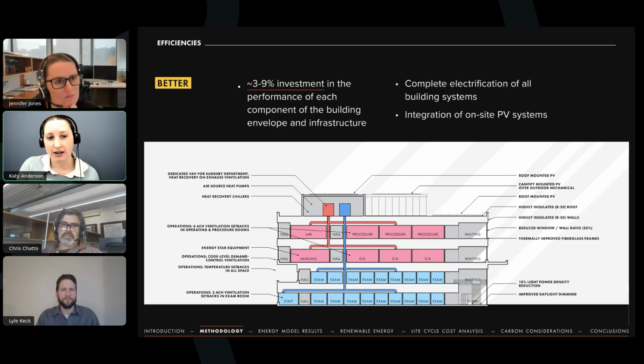So this is a fully electrified design, and the heat recovery chillers are really key in the healthcare space because of the high airflow requirements that are there for regulatory purposes. So the high airflow requirements mean that in most cases, you will have a significant amount of simultaneous heating and cooling happening in your spaces. And the heat recovery chillers allow us to achieve that conditioning at a pretty high efficiency level.